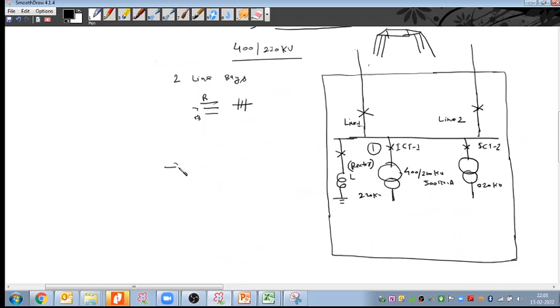The condition number one, this line should be a long transmission line. So whenever there is any long transmission line, second, this line or this trafo to which we are feeding power with the help of this transmission line, there is a light load or less loading condition. So whenever there is a long transmission line and that line is less loaded due to any load rejection, due to any major industrial load shutdown, there will be less loading on this switchyard, on this transformer, and on this transmission line.